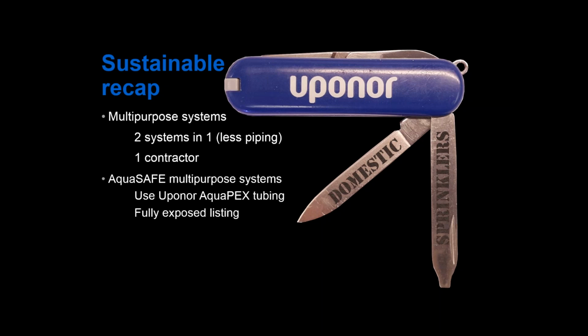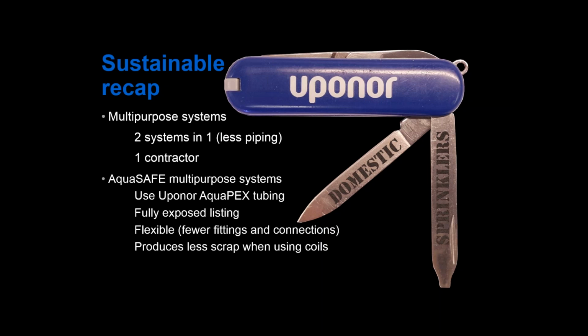We have a fully exposed listing, meaning that if I encounter a building that has floor trusses, I'm never going to have to put a sheetrock lid under there in an unfinished application. It's flexible, so I can use fewer fittings when I'm doing my installation. There aren't any elbows required to turn a corner. It produces less scrap when I'm using coils. Now, if I use PEX in straight lengths, I'm going to have similar scrap to what I had in a standalone application, but I never teach people to use straight lengths. I always teach them to use coils.